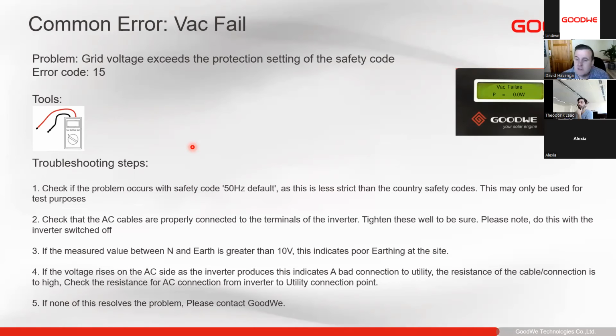If we put it to 50 Hertz and it operates correctly, then there could be an error on the utility side that you'll have to address with the utility company to rectify. We can check the AC cables are properly connected, that there are no hot connections, and make sure they are torqued properly. Then if you measure the value between neutral and earth and the voltage is greater than 10 volts, it can indicate that there is poor grounding or poor neutral connection on the inverter itself.